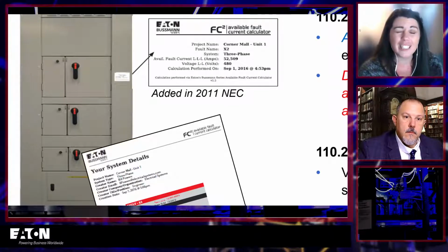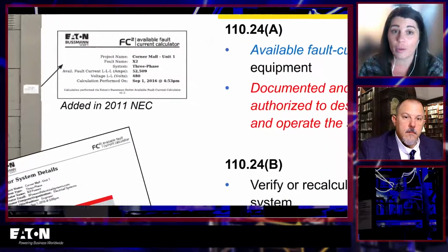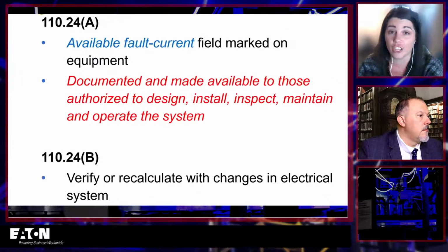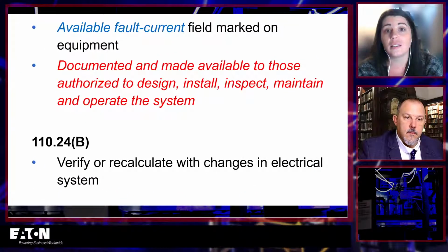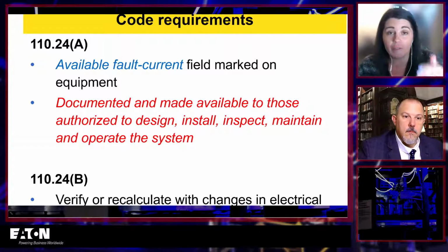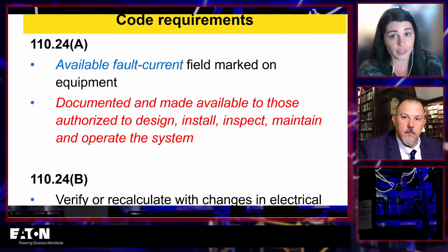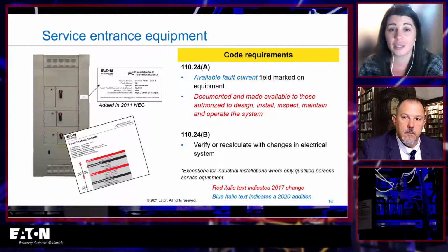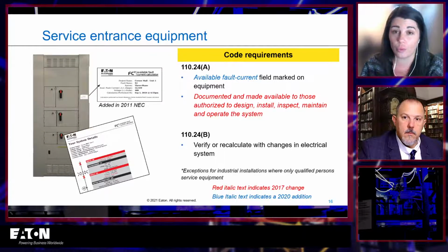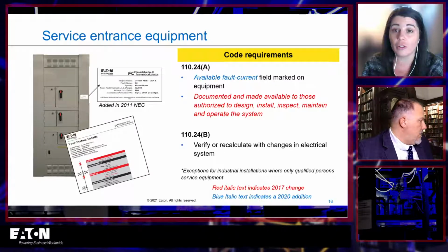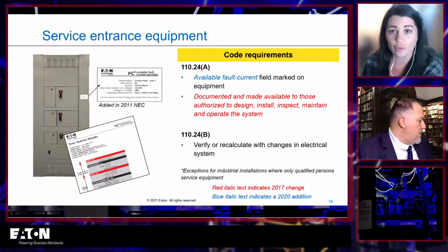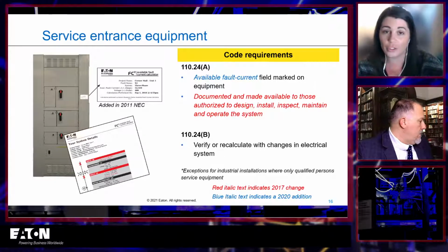In 2017, they added an additional requirement of documentation. So it's not just field marking it. It is also making a document available to anyone who is going to maintain it. A lot of these requirements for available fault current come from a simple enforcement of the code, right? You want to make sure your short circuit current ratings are greater than the available fault current. But available fault current is not like voltage, where you put a voltmeter on it and you know what the voltage of your system is.